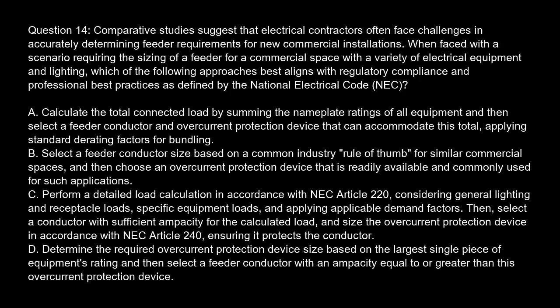Option A. Calculate the total connected load by summing the nameplate ratings of all equipment, and then select a feeder conductor and overcurrent protection device that can accommodate this total, applying standard derating factors for bundling. Option B. Select a feeder conductor size based on a common industry rule of thumb for similar commercial spaces, and then choose an overcurrent protection device that is readily available and commonly used for such applications.